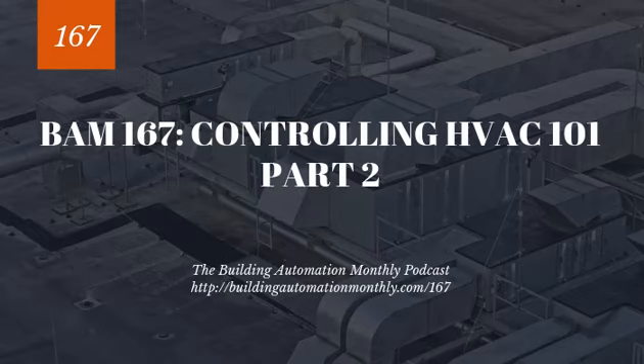So especially if you've got a CO2 requirement and you have to bring in a certain amount of fresh air for ASHRAE 62, and it's really cold out, you've got to preheat that air, so you'll tend to find preheat coils. Those will fail open typically. So when you're thinking of failure states, preheat coils will fail 100% open. Cooling coils will tend to fail closed.